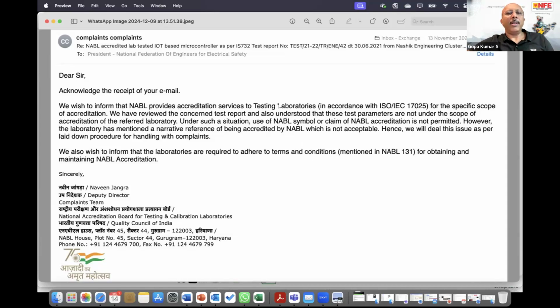First of all, I don't know how the Energy Department of Maharashtra gave an accreditation certificate to a manufacturer. Testing laboratories in accordance with ISO 17025 for specific scope of accreditation. We have reviewed the concerned test report, and also you can see here the concerned test report which is the subject of our discussion. Under such condition, the use of NABL or a claim of NABL accreditation is not permitted. However, the laboratory has mentioned a narrative reference of being accredited by NABL, which is not acceptable. Hence, we will deal with this issue as per the laid down procedure of handling non-compliance.